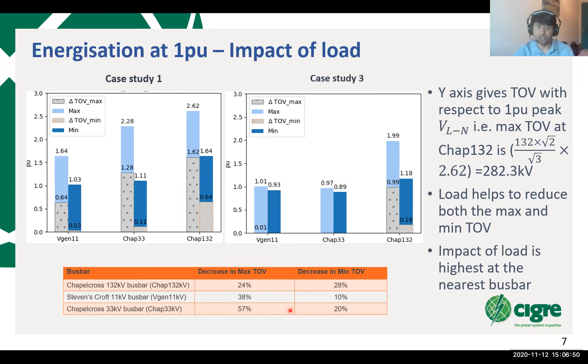Now we're going to look at the same case study, but at the time domain results, and we cannot look at all the switching instances. So the results presented here correspond to the worst case point on wave switching results for Chapel Cross 132 kV and Chapel Cross 33 kV. What we see is that in case study 1, when we don't have any primary substation energized, we observe a temporary overvoltage at both the bus bars, whereas with the demands connected, the temporary overvoltage disappears in both bus bars. In the case of the 132 kV bus bar, the switching transient can be seen here, whereas at the 33 kV bus bar, the switching transient disappears as well, and we don't have any appreciable transient at all in this bus bar.